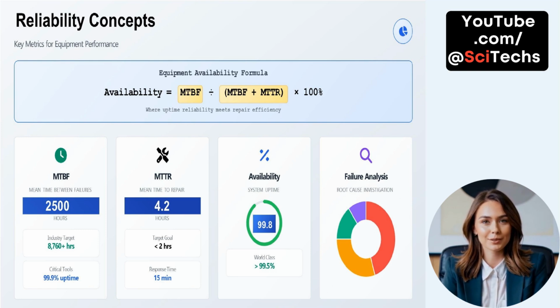MTTR, or mean time to repair, is 4.2 hours, but the target goal is less than 2 hours. Fast response is critical, with an ideal benchmark of 15-minute response time. The availability formula, MTBF divided by MTBF plus MTTR, times 100, shows the relationship between uptime and repair efficiency. With these values, availability is 99.8%, approaching world-class performance, defined as greater than 99.5%.